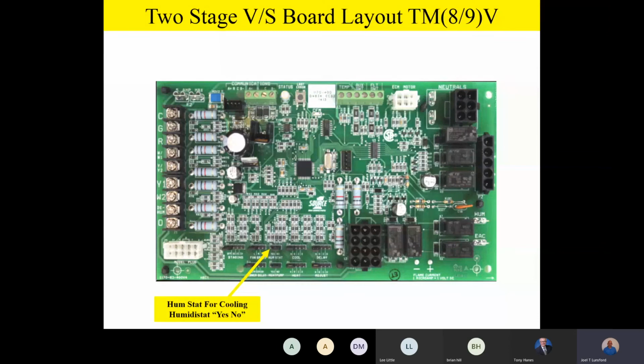Right below the humidistat jumper, you have a heat pump jumper. This is where you tell the board if it's on a heat pump or straight air conditioning system. If it's on a heat pump, you put it in the yes position, and that enables the O terminal for the reversing valve for cooling. If it's on a straight cooling unit, just a straight AC unit outside, team, remember that has to be in the no position. The heat pump jumper has to be in the no position, and then it ignores the O terminal.